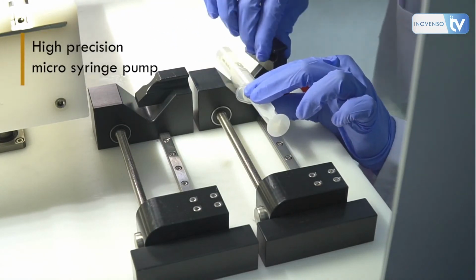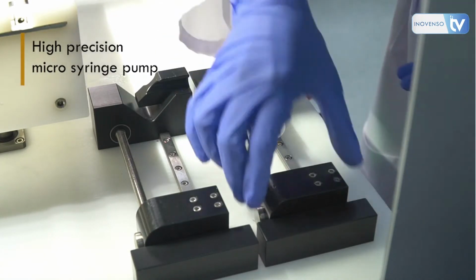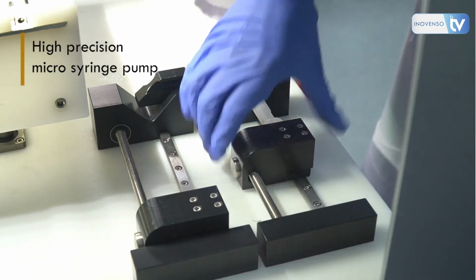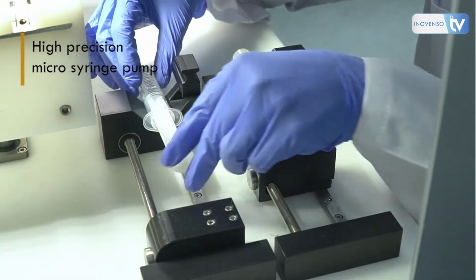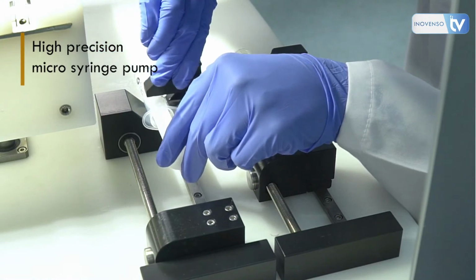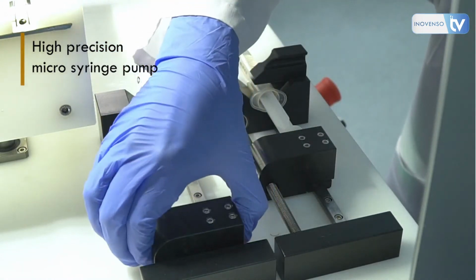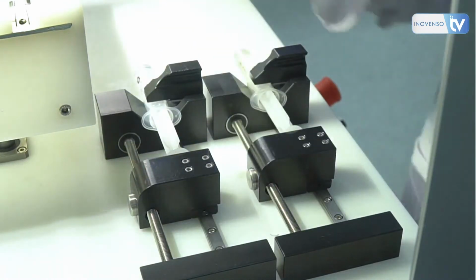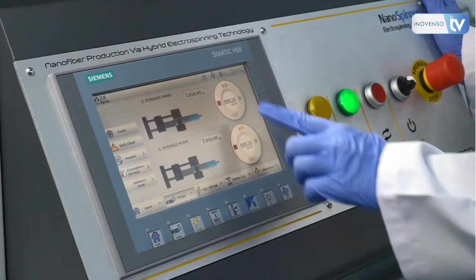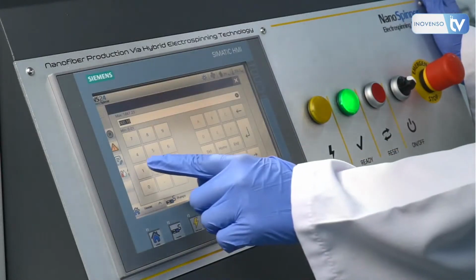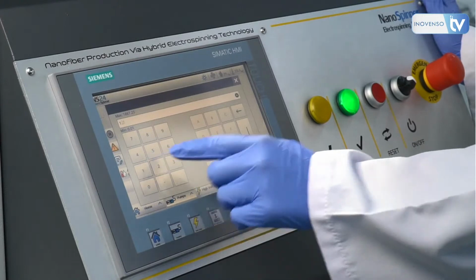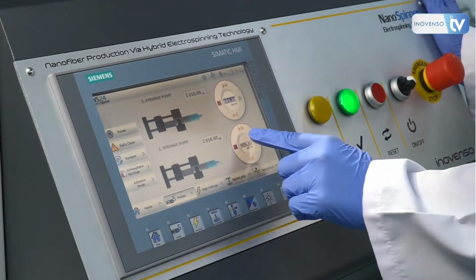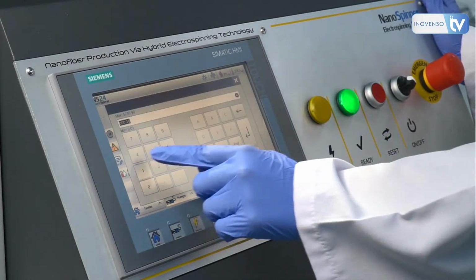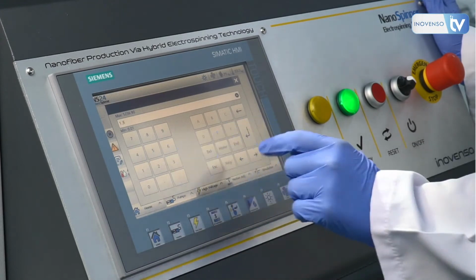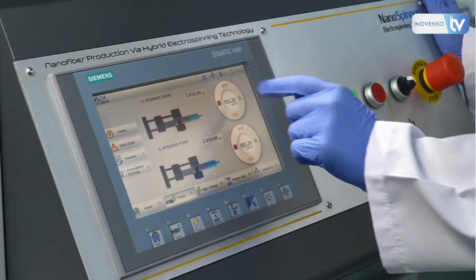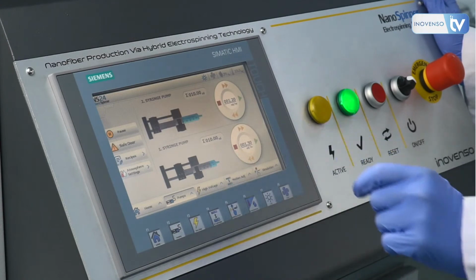You can load the polymeric solution. You can see there are two syringe pumps for the purpose of multiple solutions, like for the coaxial system, or otherwise you could just use one of them, or for composite materials, whichever you would prefer. The machine itself is all controlled via touchscreen HMI. You can set the flow rate, the volume we're putting in, the high voltage, even the spinning distance. All of that can be controlled via the touchscreen here.